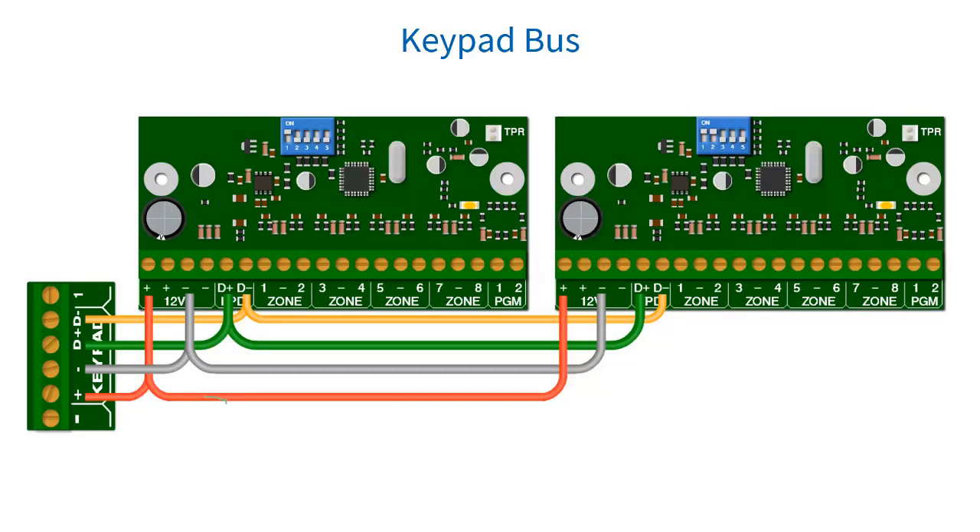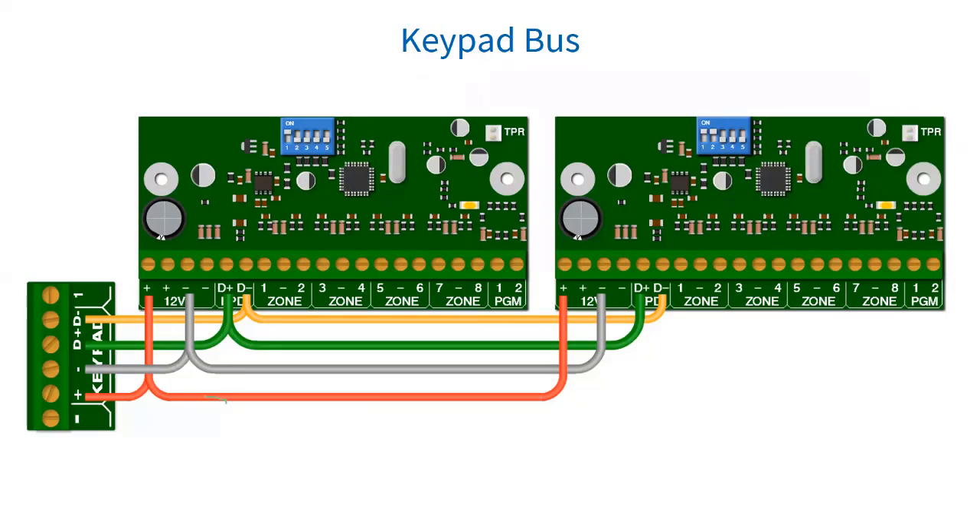This is the keypad bus. All devices connected to the bus should be connected in a daisy chain — that means one after the other — for best results. Although the X-Series panel does not need to be at the beginning or end of the daisy chain. All X-Series keypad bus devices must be powered from the X-Series panel, unless an RS-485 bus isolator is used. So it's important to wire from one device to the other in daisy chain format.